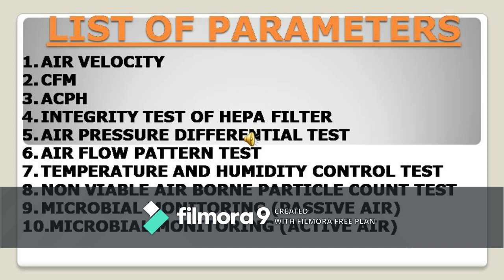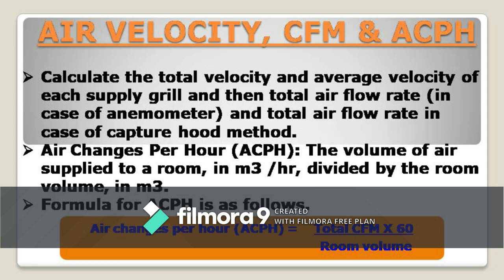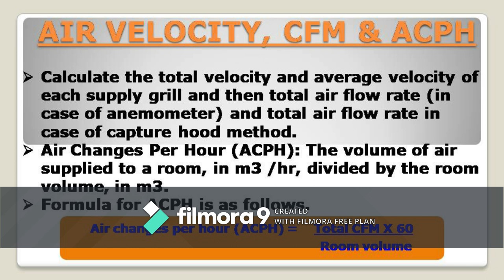First, you need to calculate the air velocity. Here we use a capture hood and anemometer instrument to check the air velocity, then we calculate the average velocity of five points. Afterwards, we calculate CFM, and then finally ACPH. The formula to calculate ACPH is: Air Changes Per Hour = Total CFM × 60 ÷ Room Volume. Remember that your ACPH acceptance criteria shall be within the design qualification specification for each area.